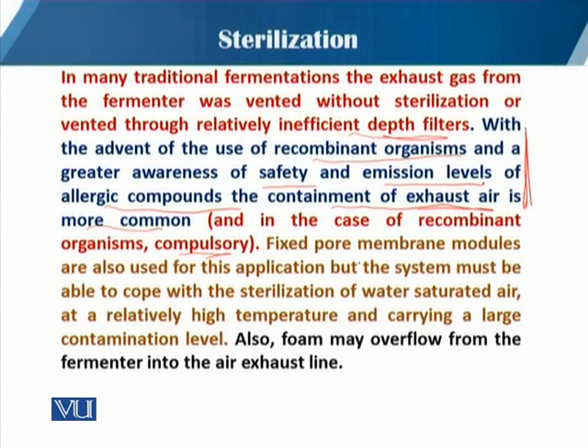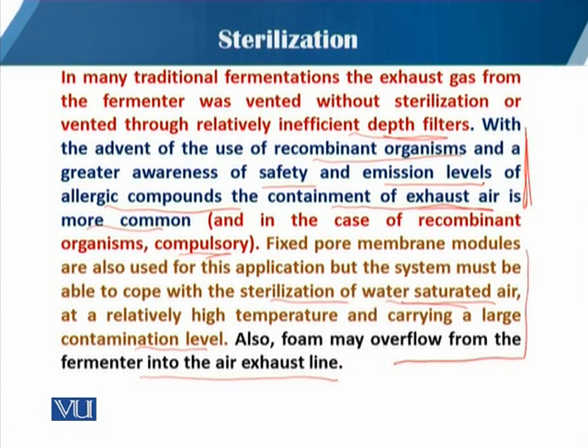Fixed pore membrane modules are also used for this application, but the system must be able to handle sterilization of water-saturated air. The exhaust air has saturated water content, is at relatively high temperature, and carries a large contamination level. Additionally, foam may overflow from the fermenter into the exhaust air. These are key limitations when selecting the sterilization process for exhaust air.